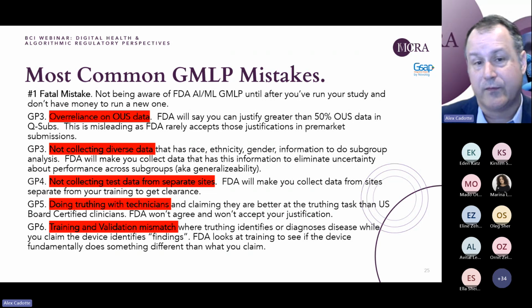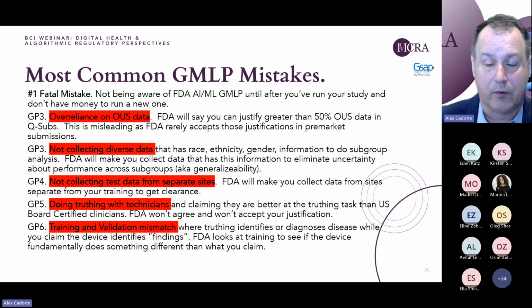Not collecting test data from separate sites. This is something where FDA has been getting more and more stringent over the years, basically to ensure that there's not bias between your test set and your training data set. This includes making sure that your validation or essentially your test data is collected from separate sites than where you collected your training data.